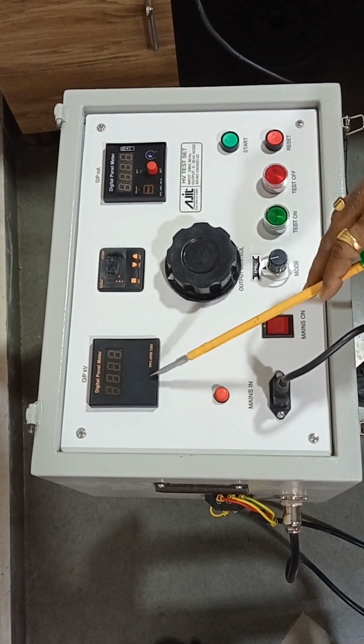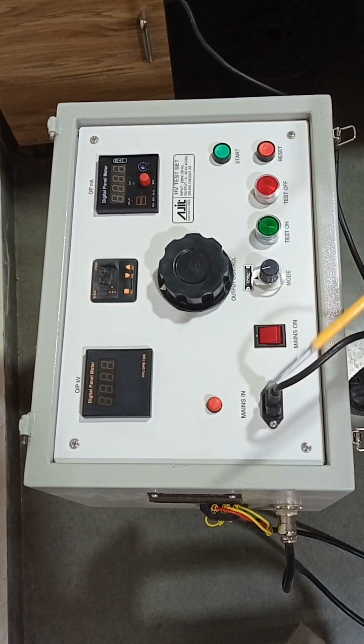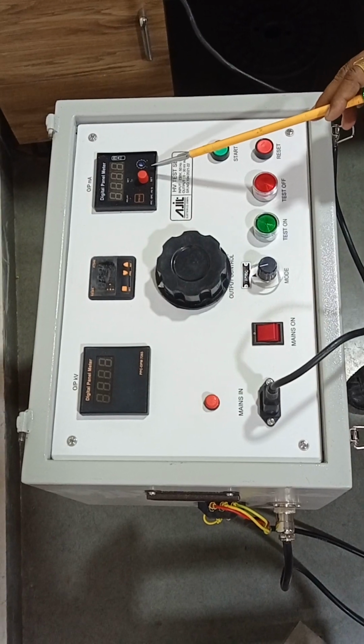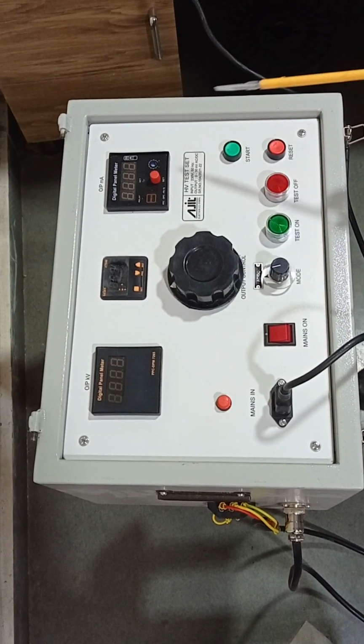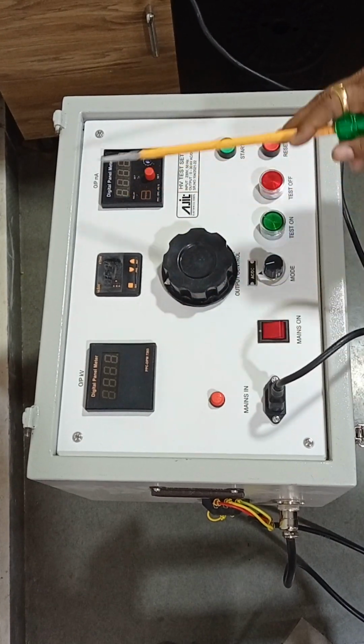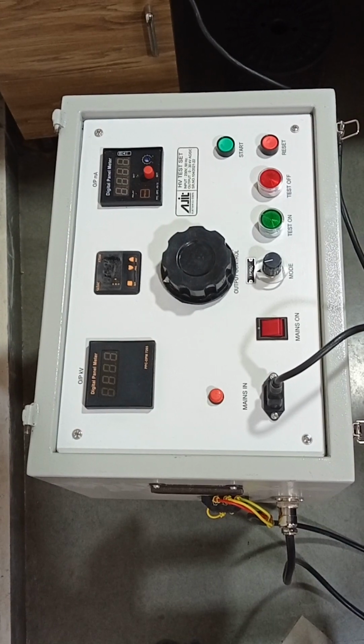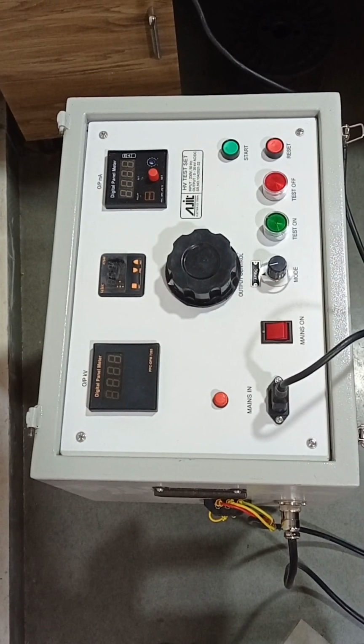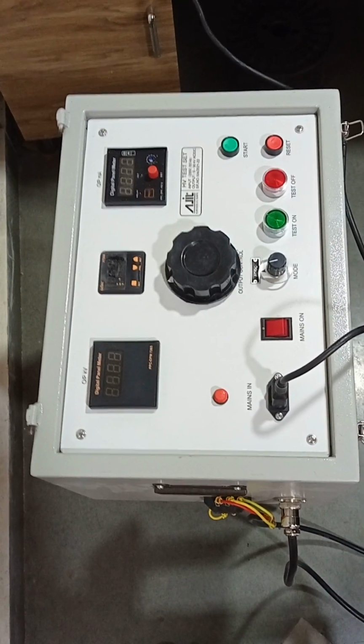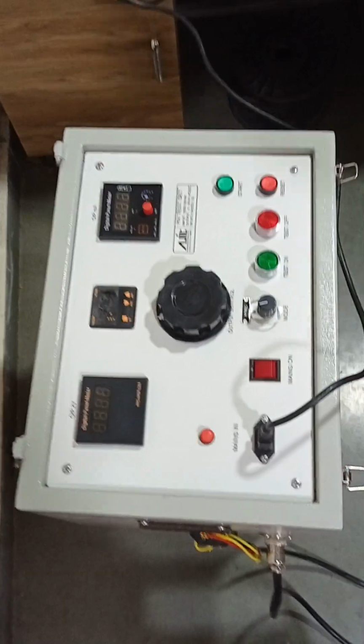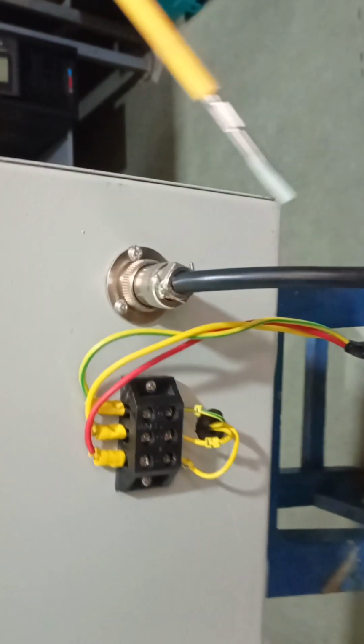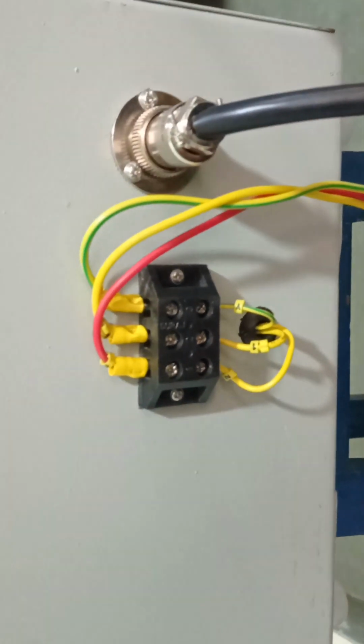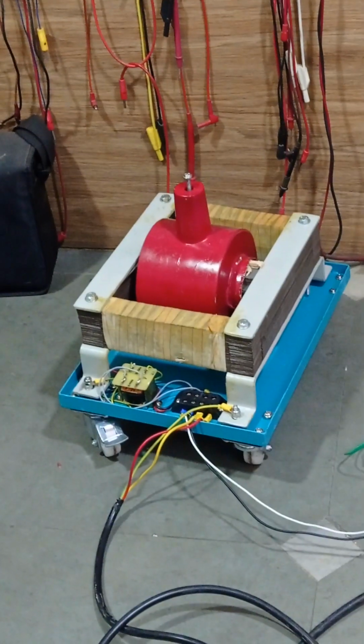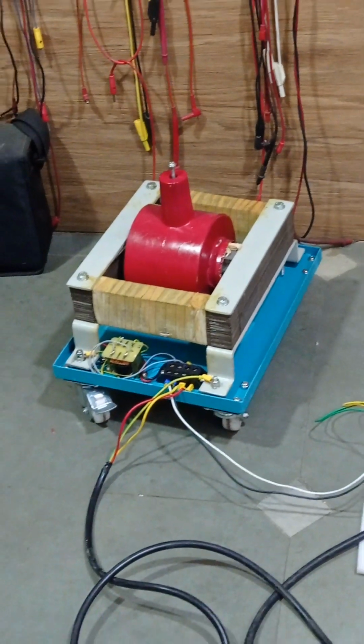This is the output kilovolt meter, kV, AC as well as DC. This is the output current meter, that is a milliampere meter, leakage current meter or trip current meter, whatever we can call it. Both these meters can operate in AC as well as in DC mode. They can read AC as well as DC parameters. So this is all about the controls. Now these are the connectors. Both the connectors go to the high voltage unit and the DC unit. We will show you the DC unit separately. All the details on how to connect are mentioned in the operating manual.